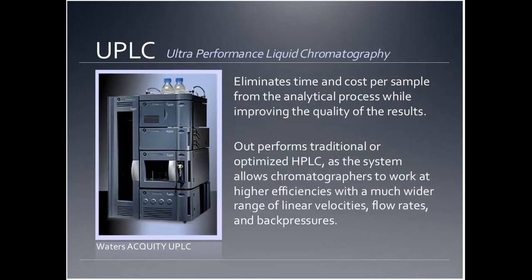Scientists have long looked at fast HPLC as a way to speed up analyses, as many HPLC procedures can be very time-consuming. The need for speed has been driven by the high numbers of samples in drug discovery labs. UPLC, or ultra-performance liquid chromatography, extends the utility of chromatography by pushing the limits of conventional HPLC — analyzing samples faster and under higher pressures, offering increased speed, resolution, and sensitivity. Lab technicians who normally see run times of 30 to 60 minutes with HPLC would benefit from UPLC, where run times are significantly reduced to as little as five minutes. In our lab, we have five UPLCs.